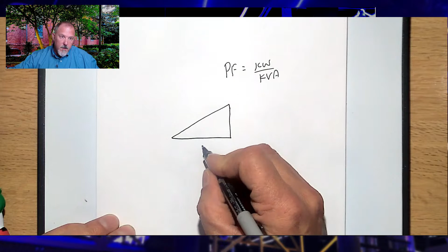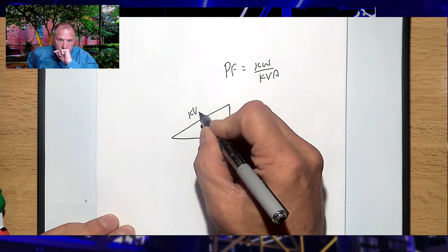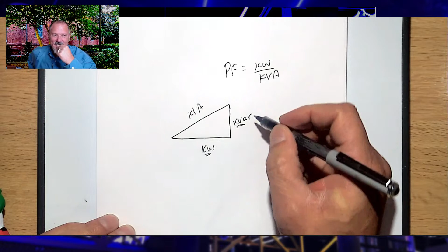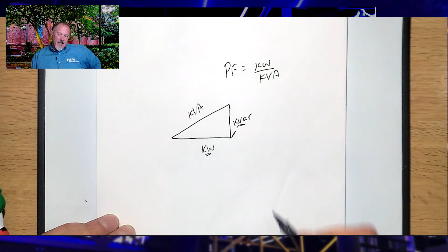Power factor equals kilowatts divided by kVA. We know this is kilowatts, this is kVAR, and this is kVA. In terms of a linear, 60 hertz load, that's exactly what you have. But in terms of harmonics, guess where they are? They're not kilowatts, not kVAR, but on this other axis—think of a three-dimensional plot.